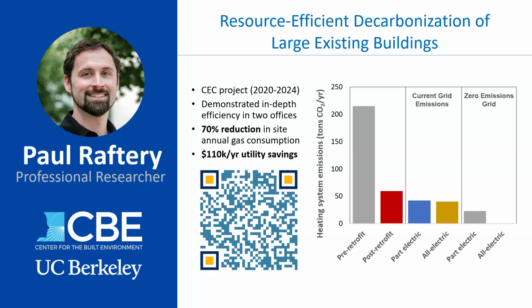On this graph here, what you're seeing is the total emissions associated with space heating in those buildings, in one of those building types, in tons of CO2 per year. The gray bar is the pre-retrofit building, which was all natural gas. Moving from the gray bar to the post-retrofit, the red bar, all we did was replace boilers with boilers and add in-depth controls efficiency measures, and we got a 70% reduction in annual natural gas from just those two measures.